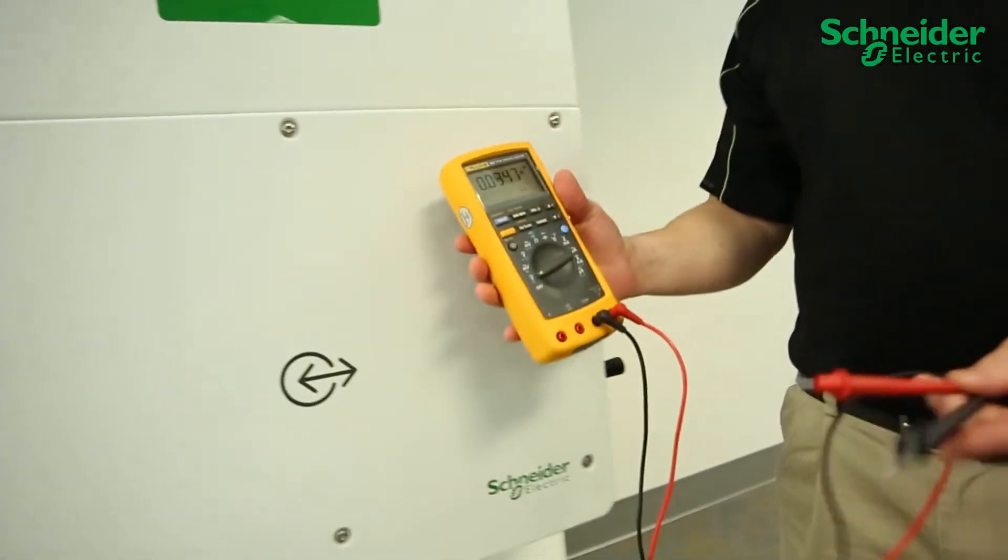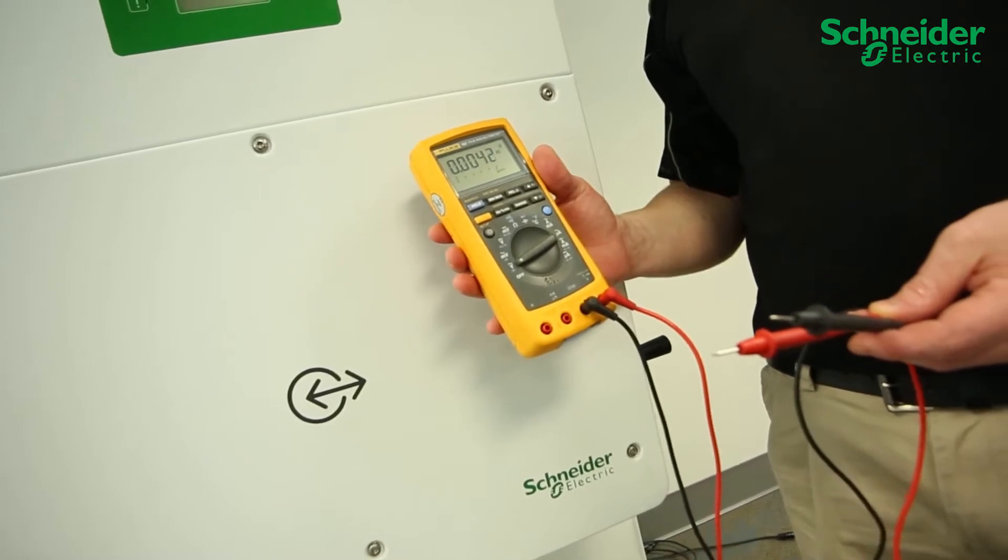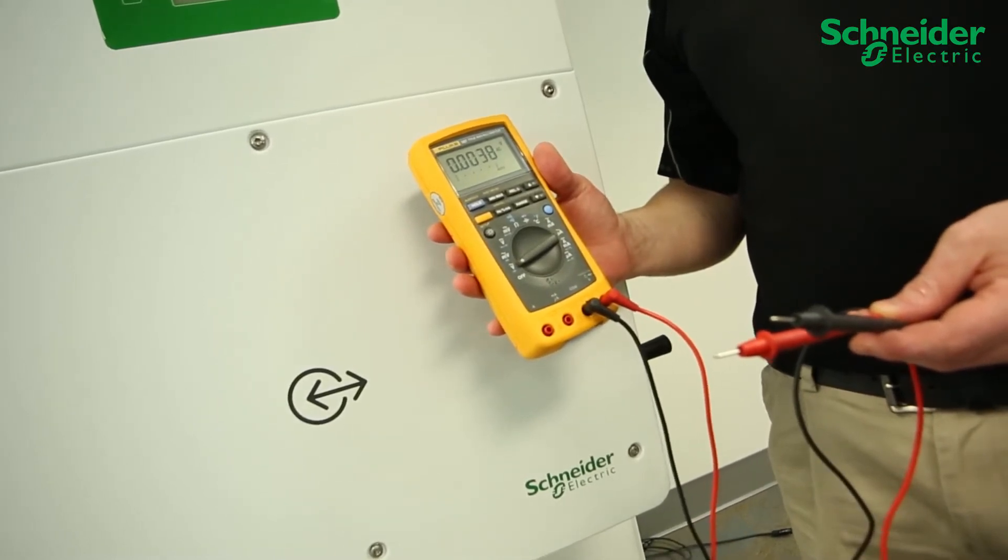Measure for the absence of voltage using the appropriate PPE equipment and minimally rated 1000 volts DC, 400 volts AC meter.